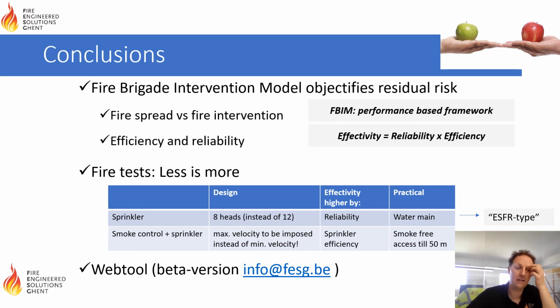The second aspect is the smoke control system. When there is a sprinkler, the design should take into account the maximum velocity instead of minimum velocity, which will increase the sprinkler efficiency. Practically speaking, we should be designing smoke control systems on a smoke-free access till 50 meters, for instance. Or you could even think about smoke clearance type of smoke control systems. But having high ventilation, high velocities will clearly have a negative impact on your sprinkler. So it's a choice to be made.